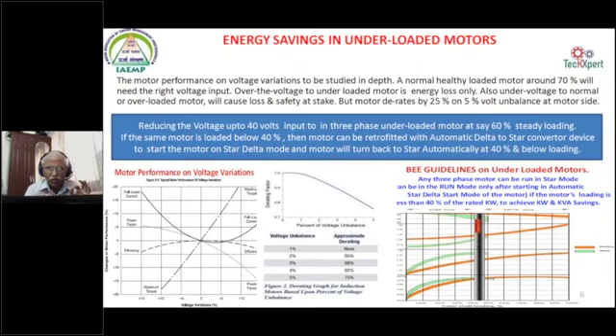So whether the motor is loaded correctly or rated correctly, whatever you are getting on the EB, just confirm, these are all the end-to-end losses. I am having my voltage probe at the middle point of the plant. It can be at the tail end too. Whenever I am switching the next motor on and off, a high capacity motor, say 55 kilowatt or 75 HP or 37 kilowatt, whichever it may be, once you have a dip and dim of the voltage drop, there is a probability of some dry loose contacts in the SSB. So these are all the areas.